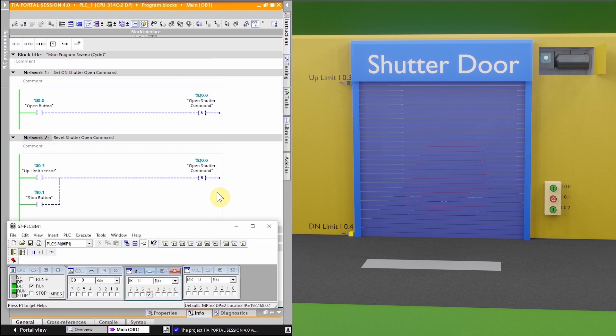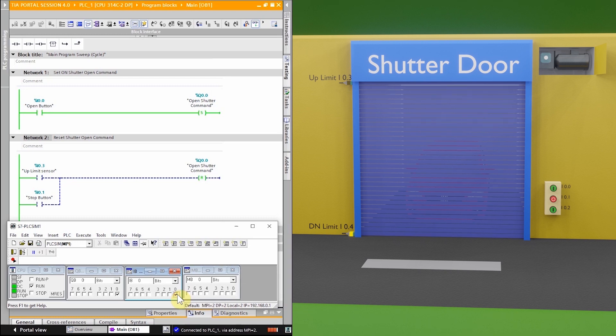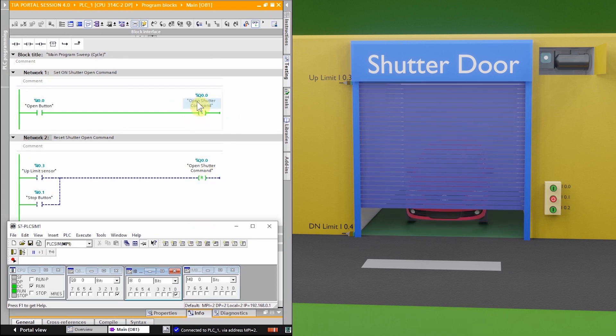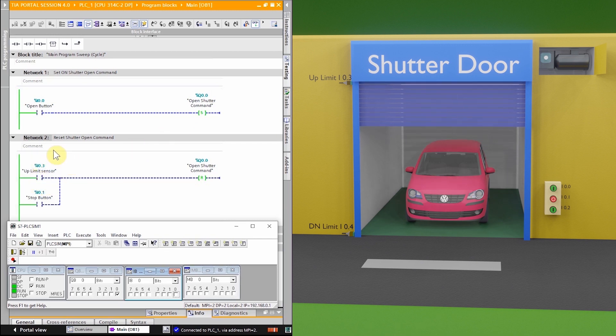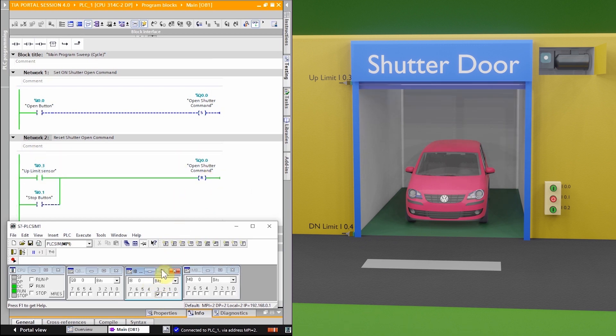Right now the shutter is fully closed and we want to open it. We press the open button I0.0, and the shutter open command is set on. It stays on even after releasing the push button, and the shutter starts to open. Once the shutter is fully open, the up limit sensor I0.3 turns on, which resets output Q0.0, and the shutter motor stops at the fully open position.